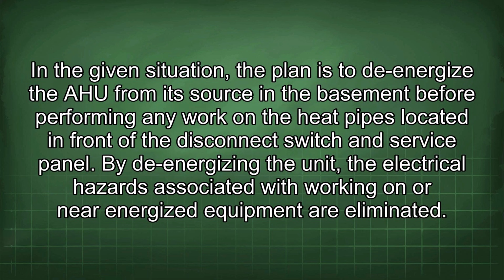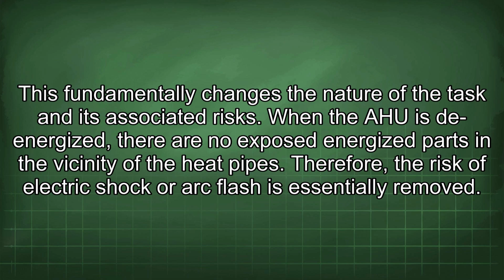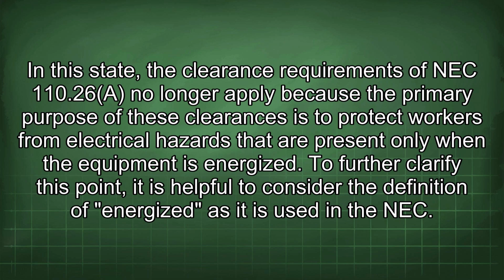In the given situation, the plan is to de-energize the AHU from its source in the basement before performing any work on the heat pipes located in front of the disconnect switch and service panel. By de-energizing the unit, the electrical hazards associated with working on or near energized equipment are eliminated. This fundamentally changes the nature of the task and its associated risks. When the AHU is de-energized, there are no exposed energized parts in the vicinity of the heat pipes. Therefore, the risk of electric shock or arc flash is essentially removed. In this state, the clearance requirements of NEC 110.26 no longer apply because the primary purpose of these clearances is to protect workers from electrical hazards that are present only when the equipment is energized.